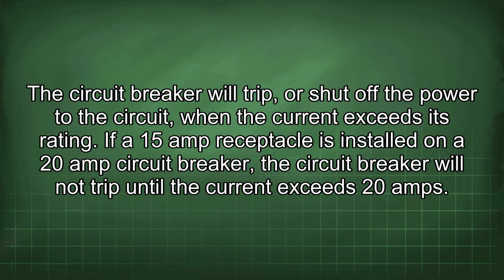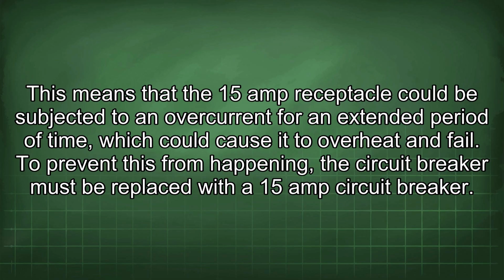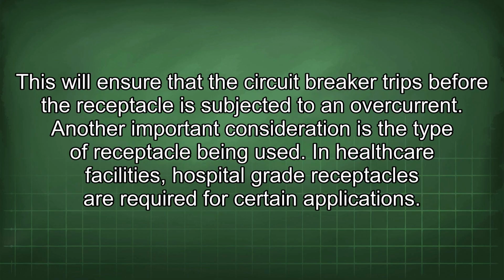If a 15 amp receptacle is installed on a 20 amp circuit breaker, the circuit breaker will not trip until the current exceeds 20 amps. This means that the 15 amp receptacle could be subjected to an overcurrent for an extended period of time, which could cause it to overheat and fail. To prevent this from happening, the circuit breaker must be replaced with a 15 amp circuit breaker. This will ensure that the circuit breaker trips before the receptacle is subjected to an overcurrent.